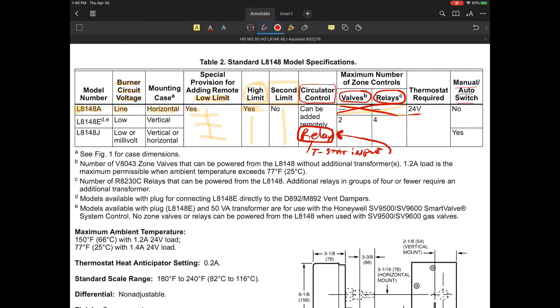Thermostat input required, all they're telling you is it's got to be capable of handling 24 volts. That could be any relay or anything like that. And then, of course, what they call a manual auto switch. Some of these units have a manual auto switch, which allows you to either manually keep the boiler temperature up all the time, or allow the burner circuit to cycle with a heating demand. That's what they mean by the auto manual switch.